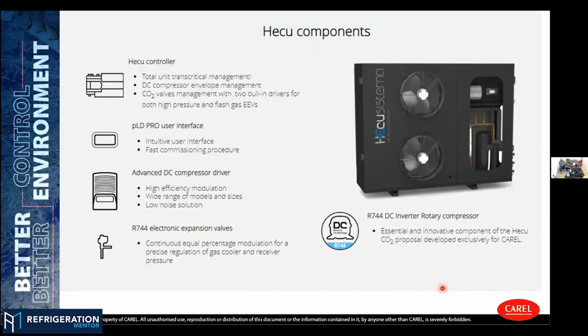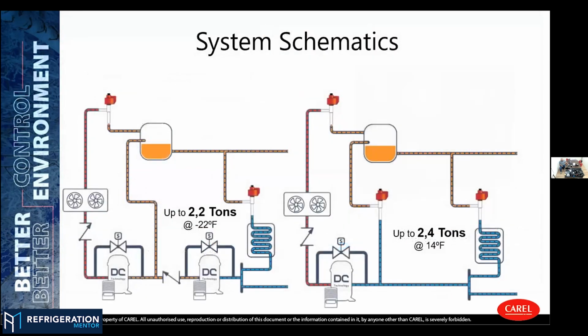Another approach is the HECU platform, that is the high efficiency condensing unit. Basically, here we have all the controller and the components in order to make a condensing unit with CO2, both subcritical or transcritical. The software can manage both of those applications. And also the HPV valve and the flash gas bypass valve in case needed. So we could manage both applications in transcritical systems. This is a schematic of the system.